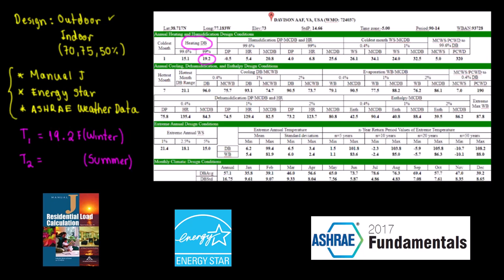The 99th percentile refers to the frequency of occurrence. For summer we're talking about cooling, and we have more options: 0.4%, 1%, and 2% percentile. Since we're matching the 99th percentile approach, we'll use the 1% percentile. This 1% means there is only a 1% probability that the temperature will go above this design temperature.